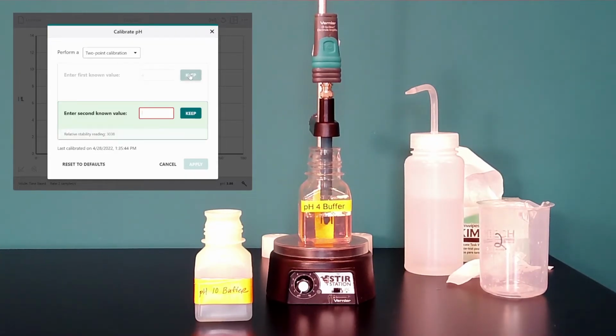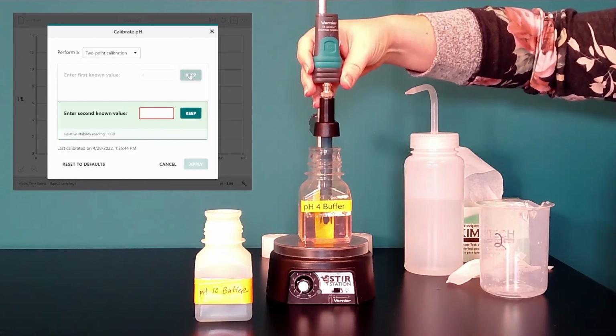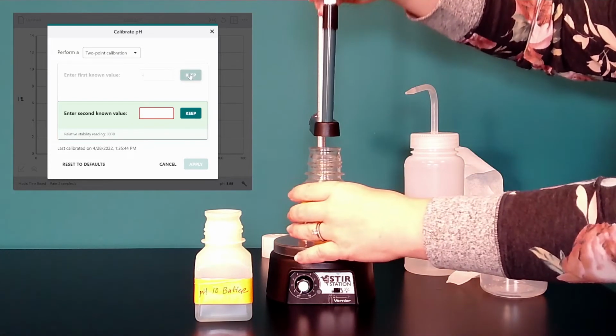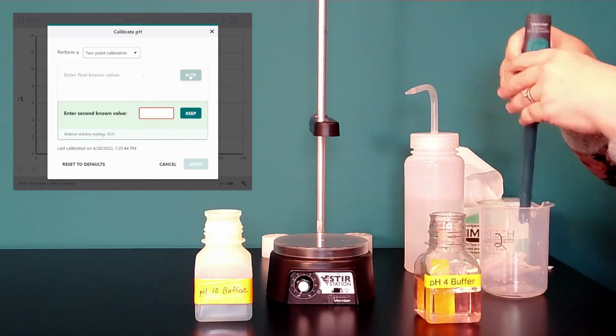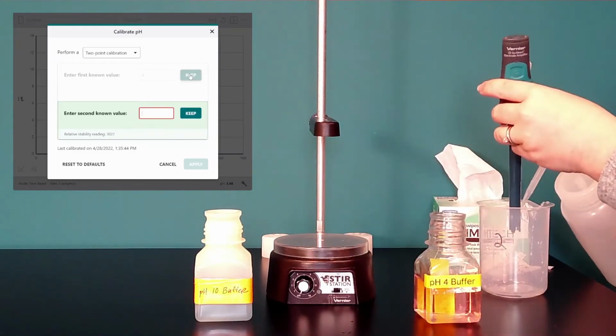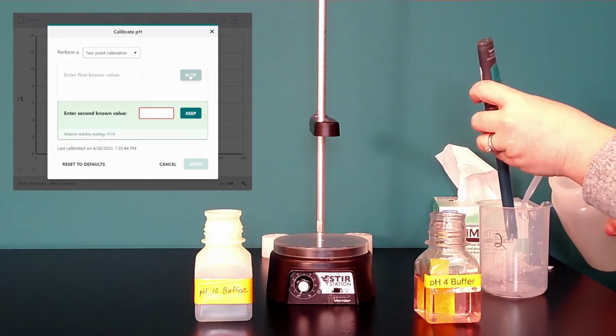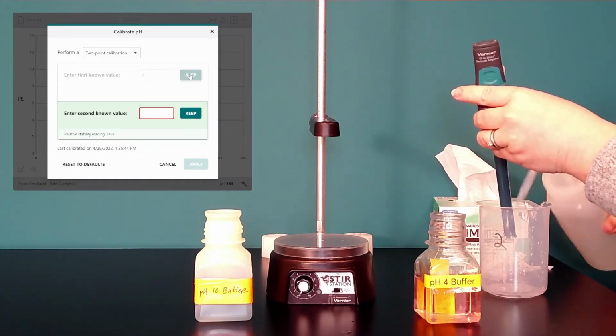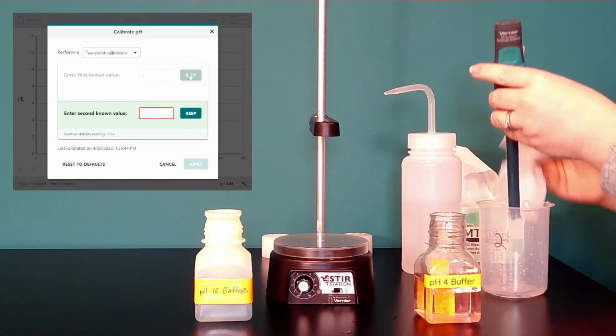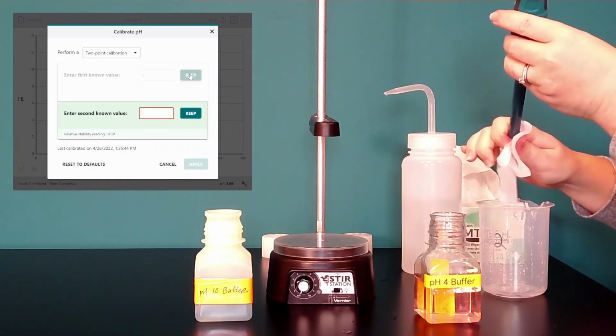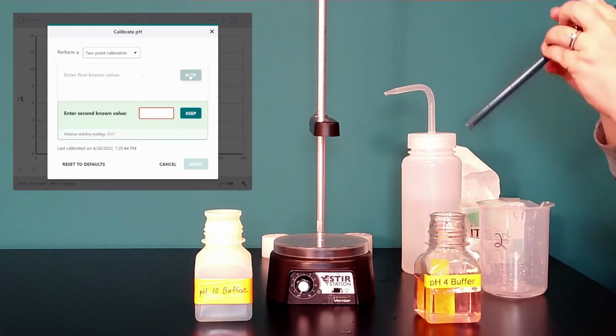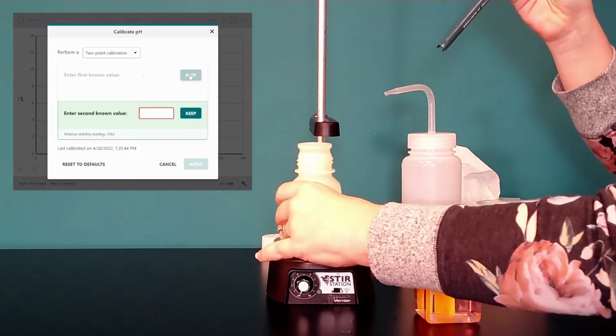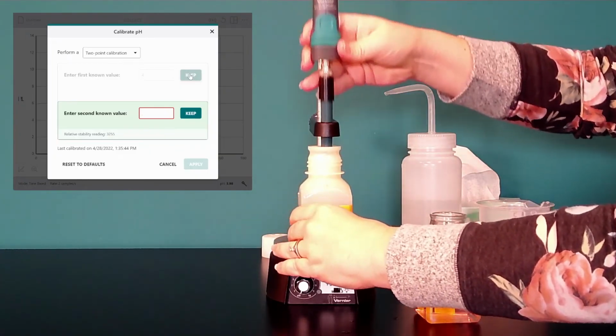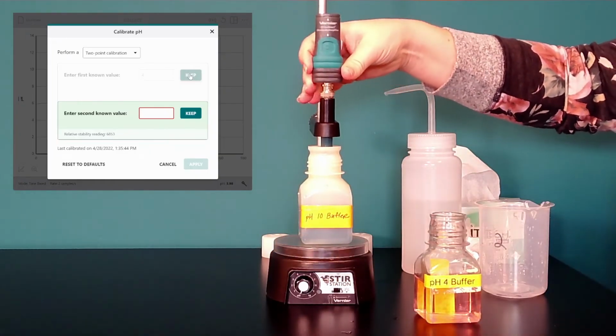For the second value, I'm going to be using a pH 10 buffer, so I need to remove my pH sensor from the pH 4 buffer and rinse it with deionized water. I then want to pat it dry with a Kimwipe and put it in my pH 10 buffer solution.